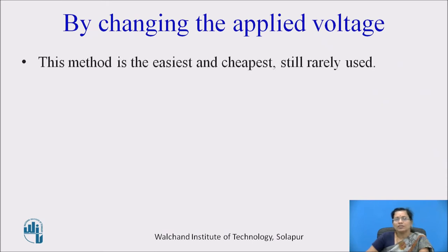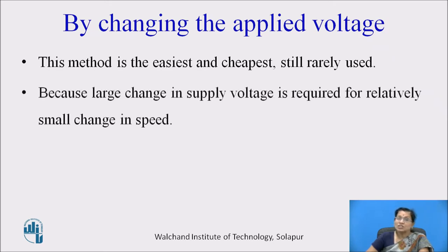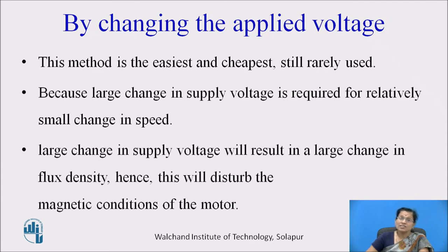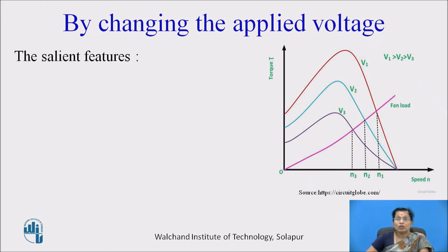Let us discuss about this method. This method is the easiest and cheapest, still rarely used because a large change in supply voltage is required for a relatively small change in speed. A large change in supply voltage will result in large change in flux density, hence this will disturb the magnetic condition of the motor. And if the motor goes into saturation, that will affect the working of the motor. The graph indicates the torque and voltage relation — as we change the voltage, the maximum torque also changes. You can see V1 is greater than V2 is greater than V3, and the maximum torque also increases with increase in voltage.